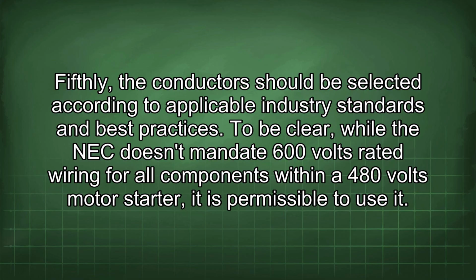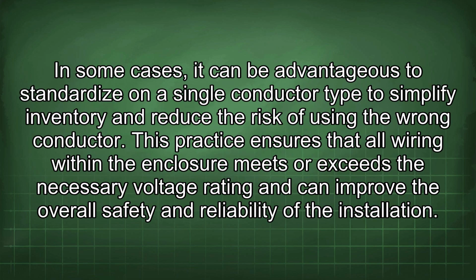To be clear, while the NEC doesn't mandate 600 volt rated wiring for all components within a 480 volt motor starter, it is permissible to use it. In some cases, it can be advantageous to standardize on a single conductor type to simplify inventory and reduce the risk of using the wrong conductor. This practice ensures that all wiring within the enclosure meets or exceeds the necessary voltage rating and can improve the overall safety and reliability of the installation.